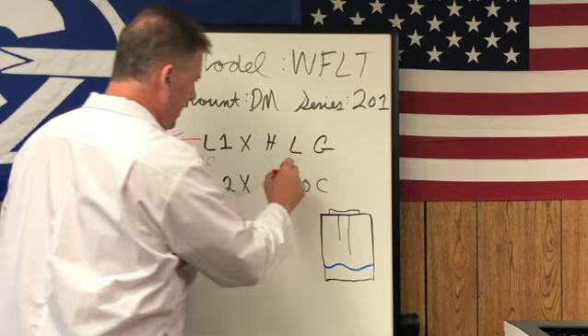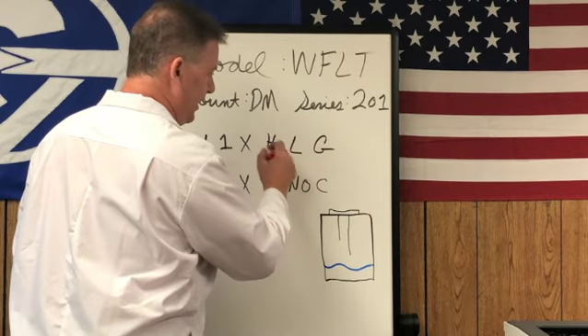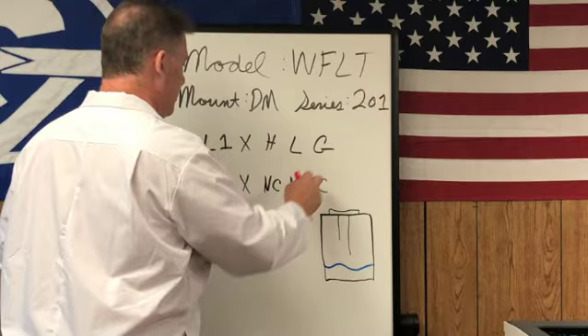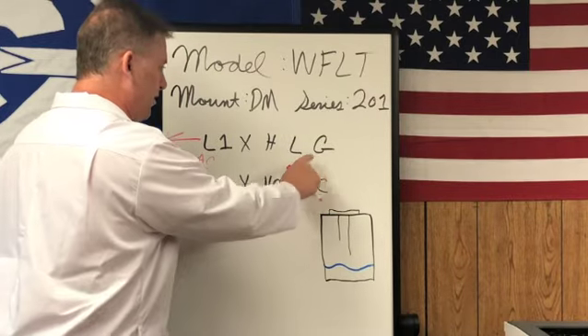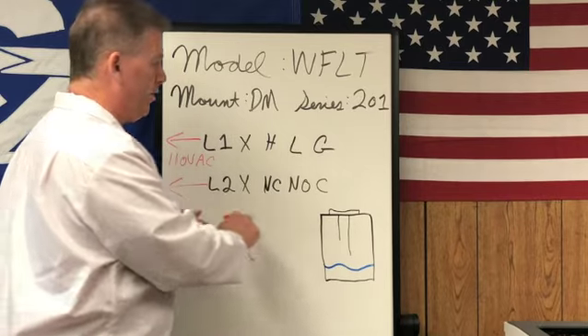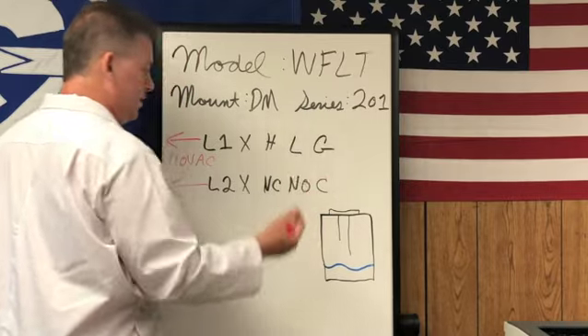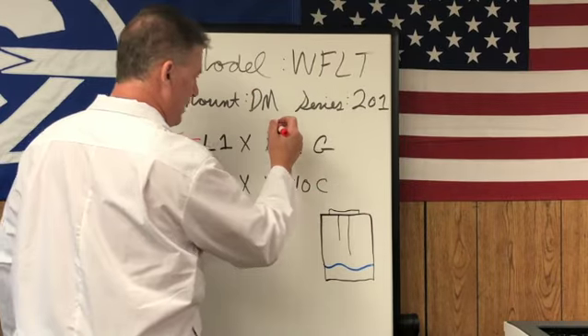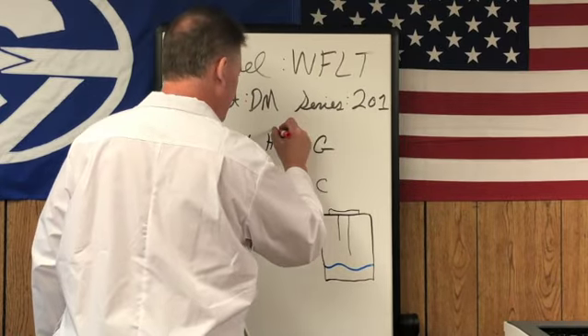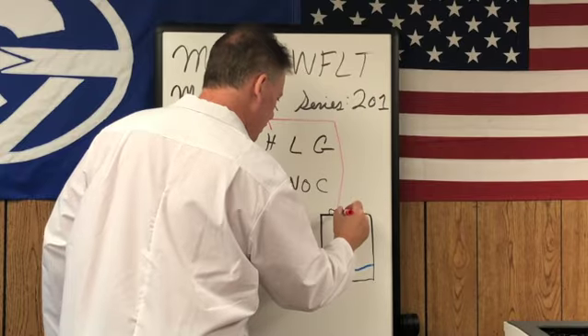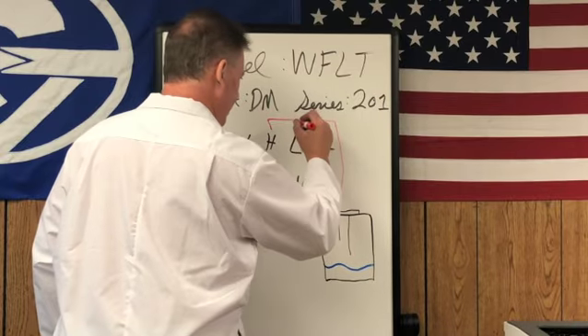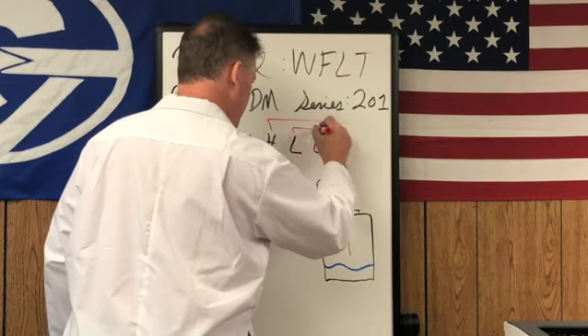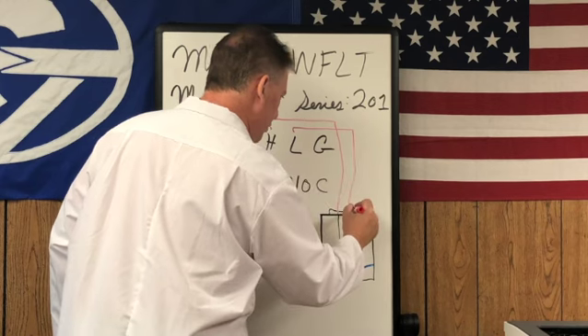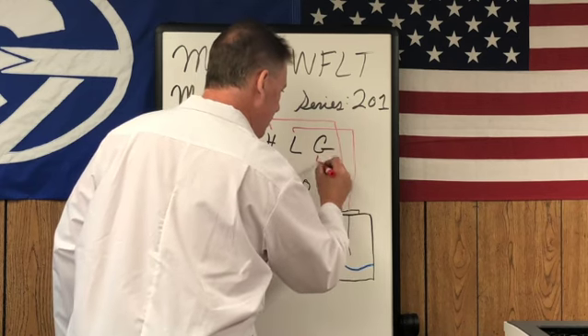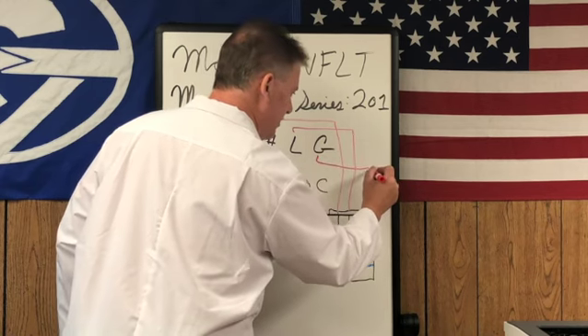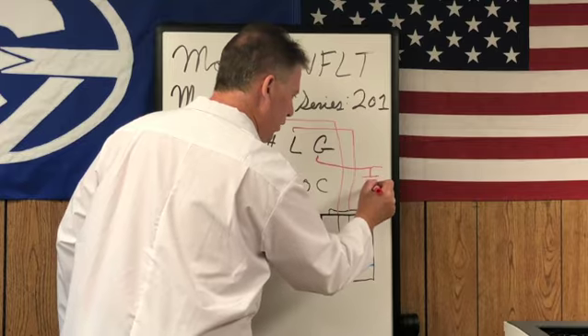So we take the high level. We're going to take HL and G, high level and ground. The ground, just to let you know, has nothing to do with the line power. This is only for the sensing circuit, so it's going to be grounded to the tank. I'll do that in a second. We take the high terminal and bring it to the high level probe, and the low terminal and bring it to the low level probe. And then the ground, I'll bring it out here so you can see. Any good earth ground will work.